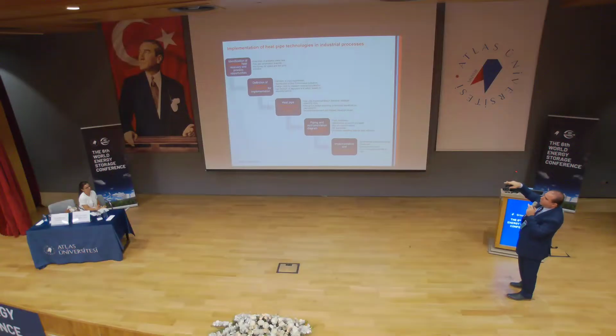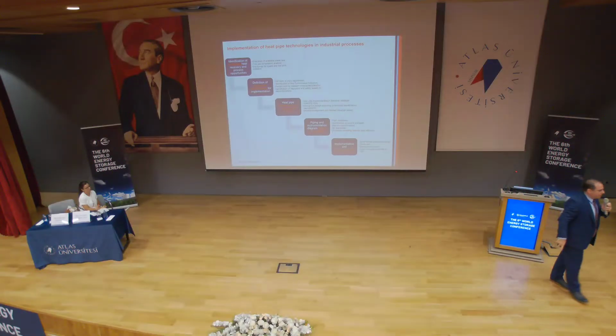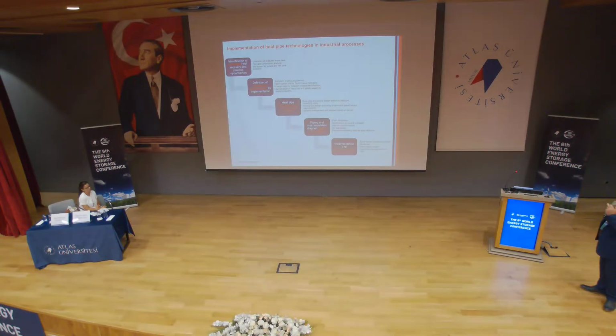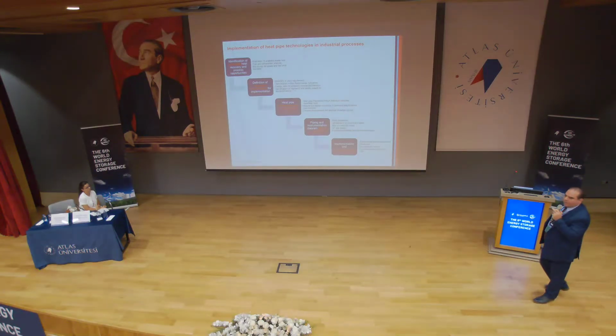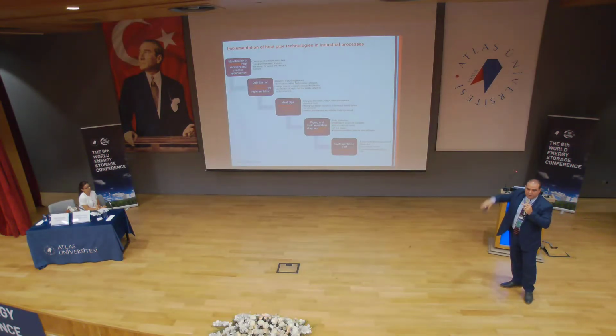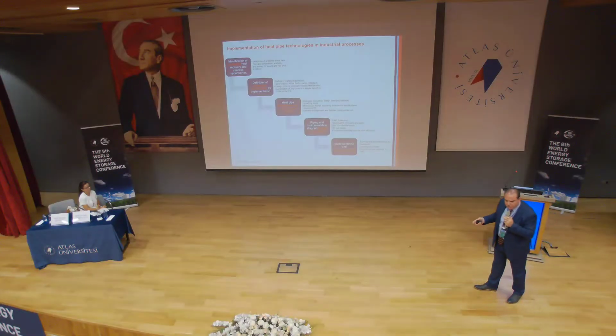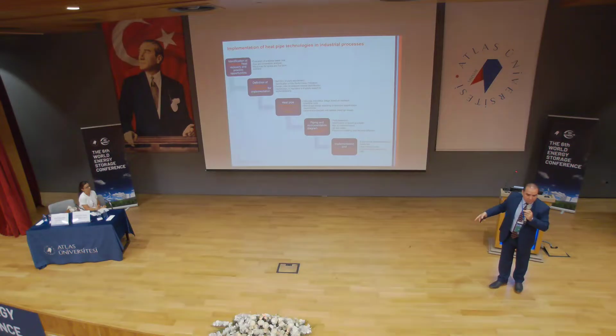So we follow the waste heat recovery case building process by identifying the streams. When a company comes and says, look, I have these fumes coming out, can you design a heat exchanger? It sounds simple, it's not. You have to look at the fumes, the composition, the temperatures. If I am to recover the heat, what do I do with the heat? That's where this conference is very important.